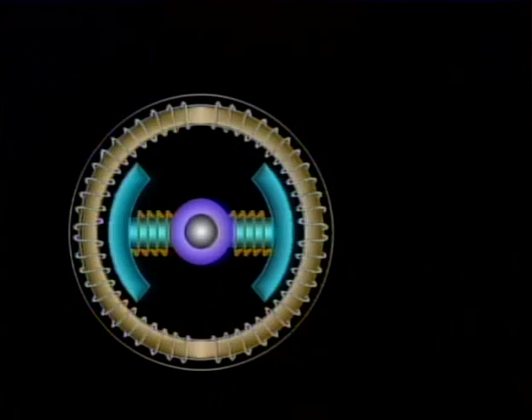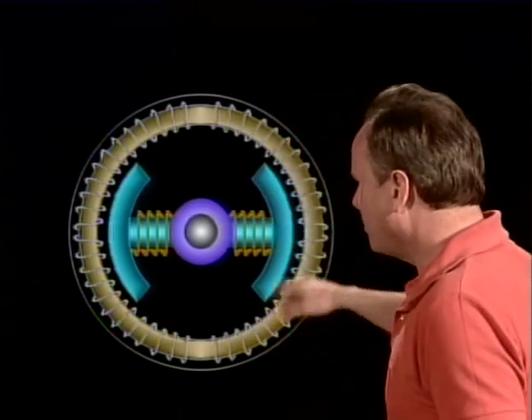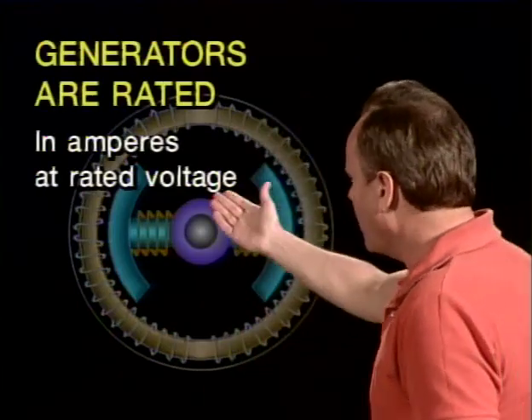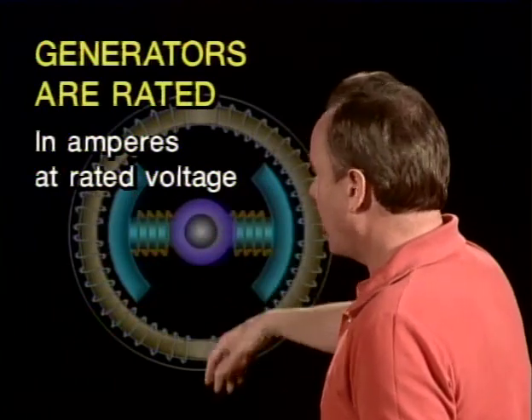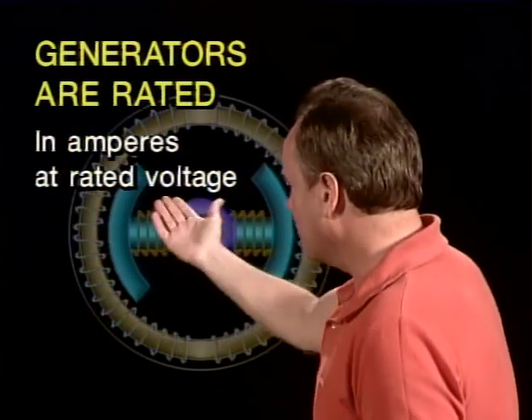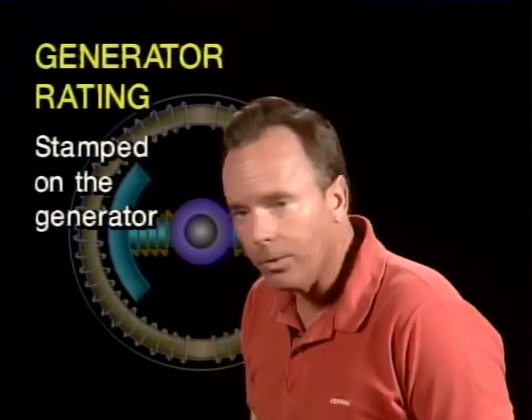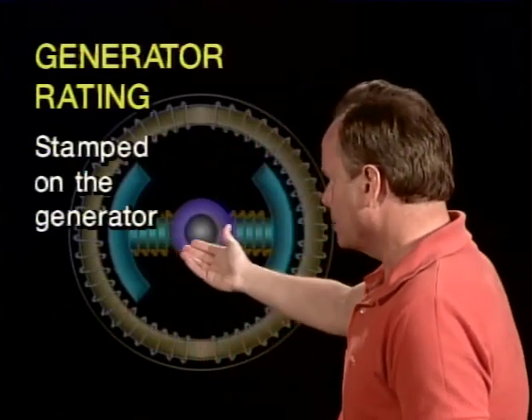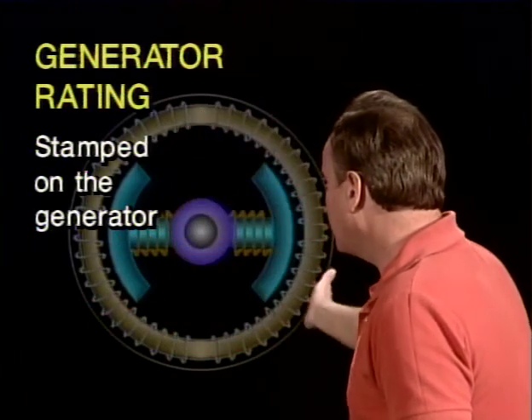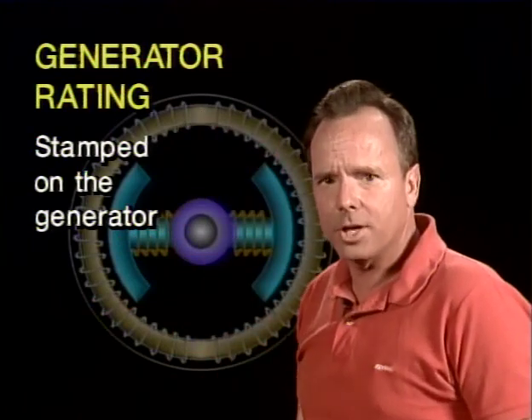Now let's you and I take a look at motors and generators, and they're electrically and mechanically very similar to each other. They have all the same components, and they're just wired a little bit differently. We'll talk about that. First of all, let's take a look at how generators are rated. Well, generators are rated in amperes at rated voltage. How are generators rated? In amperes at rated voltage. Now, the generator rating will usually be found stamped on the generator somewhere. So look around the outside of the generator, and you'll usually find the generator rating.